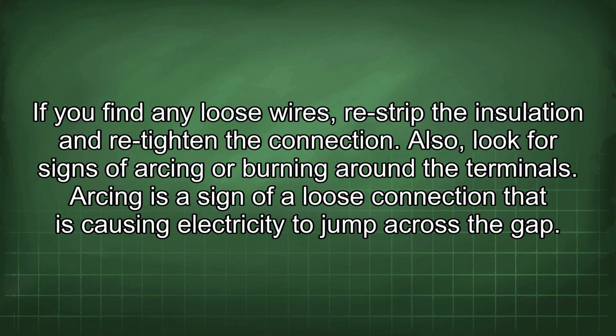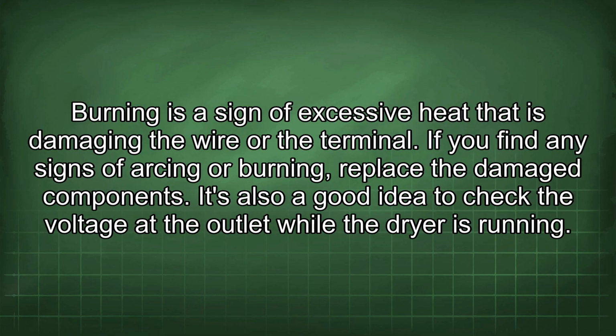Also, look for signs of arcing or burning around the terminals. Arcing is a sign of a loose connection that is causing electricity to jump across the gap. Burning is a sign of excessive heat that is damaging the wire or the terminal. If you find any signs of arcing or burning, replace the damaged components.